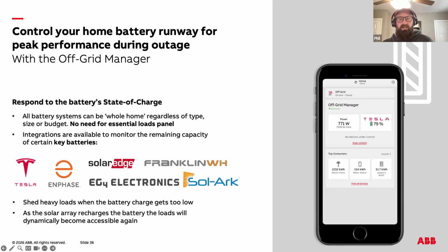Real-time power monitoring lets the system constantly watch the actual load on a service or circuit. That allows it to automatically reduce or pause loads before anything becomes overloaded. Instead of sizing everything for the worst-case scenario, the system can safely operate within the limits of the existing electrical system. When running on battery, the limiting factor isn't just power, it's how much energy is left.